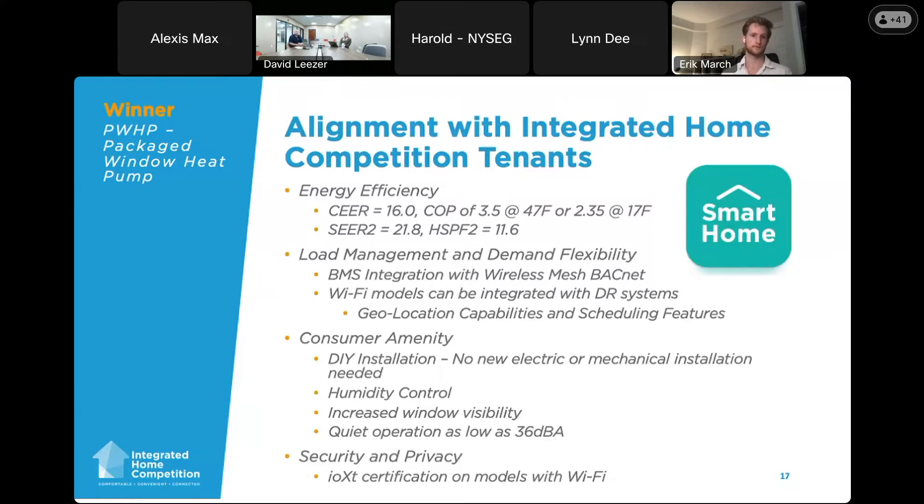From an energy efficiency standpoint with the integrated home competition criteria: the typical window AC efficiency rating is CEER (Combined Energy Efficiency Ratio). This unit currently has the highest value at 16. On the heating side, we have a COP of 3.5 at 47°F and 2.35 at 17°F, which was one of the targets from the NYPA spec. We also did CEER2/240V testing: we achieved a SEER2 of 21.8 and an HSPF2 of 11.6, which should translate better for most CE membership compared to the CEER rating typical for window ACs.